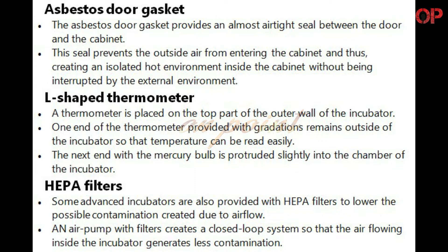Asbestos Door Gasket: The asbestos door gasket provides an almost airtight seal between the door and the cabinet. This seal prevents the outside air from entering the cabinet, thus creating an isolated hot environment inside the cabinet without being interrupted by the external environment. L-Shaped Thermometer: A thermometer is placed on the top part of the outer wall of the incubator. One end of the thermometer, provided with gradations, remains outside of the incubator so that temperature can be read easily. The other end with the mercury bulb is protruded slightly into the chamber of the incubator.